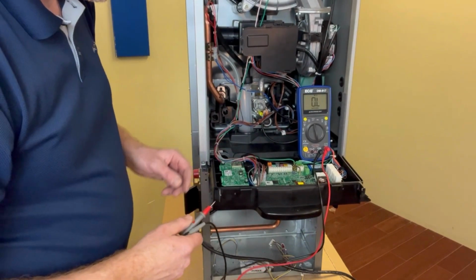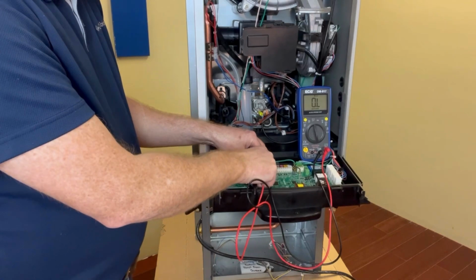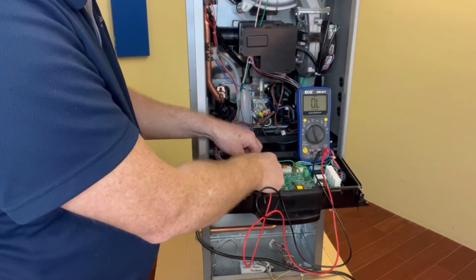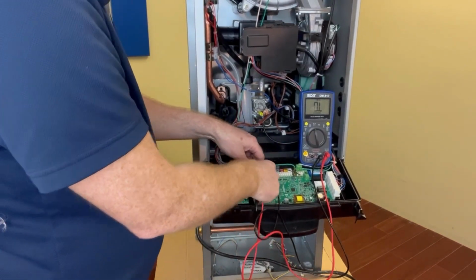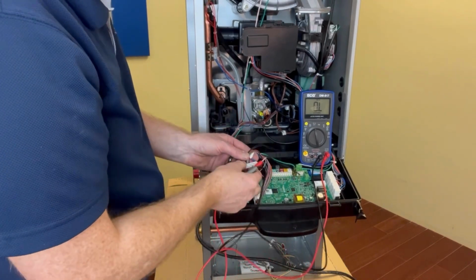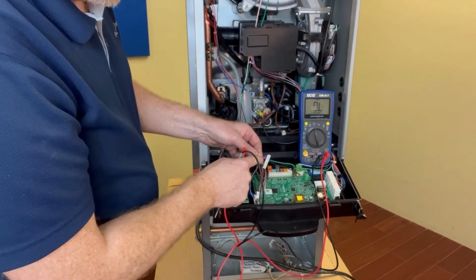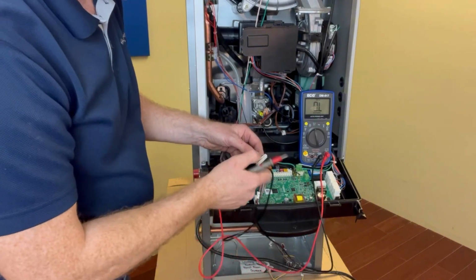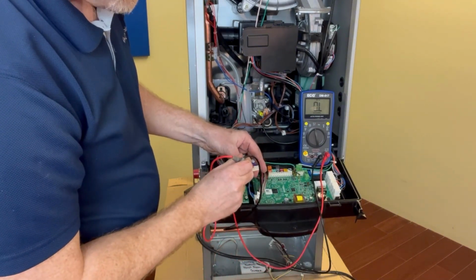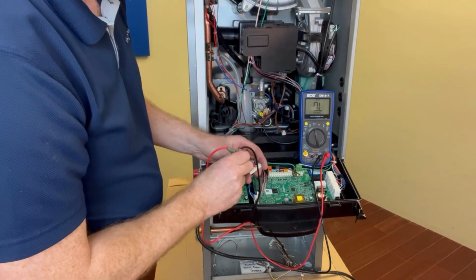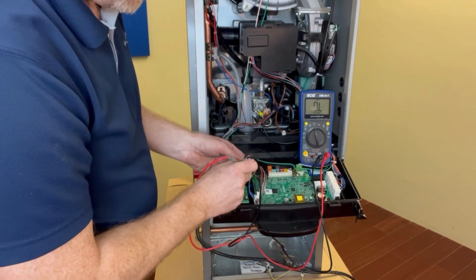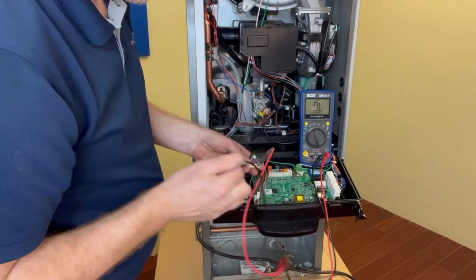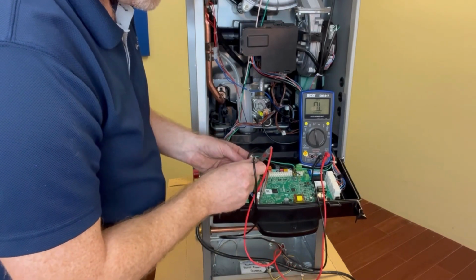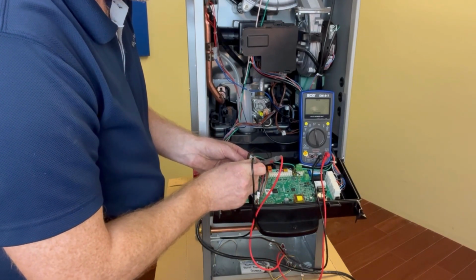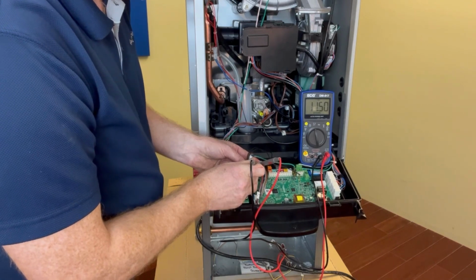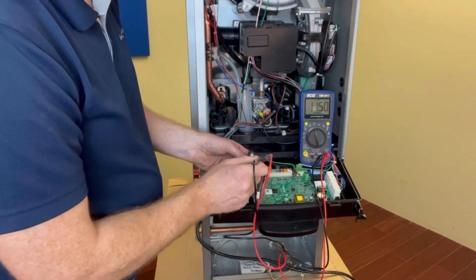Now that I've moved to the circuit board, I'm going to remove connector 26 on the bottom left-hand side of the control board. These can be a little stiff. Just press on it, it will come off. Identify the two red wires, and now we're going to take a reading at this plug with our sensor plugged in. If we get the exact same reading, that means both the wires and the sensor are probably okay. So I get a reading that's basically the same.